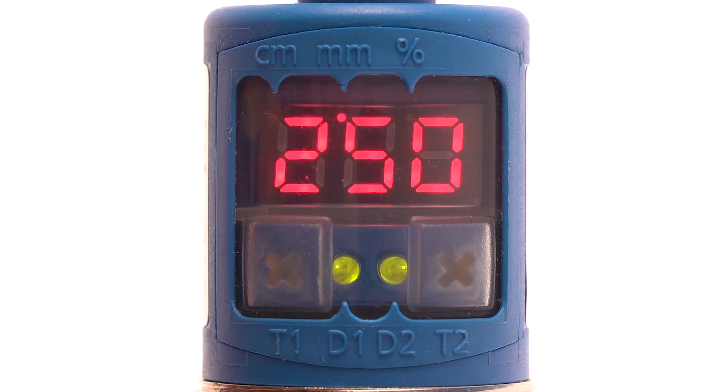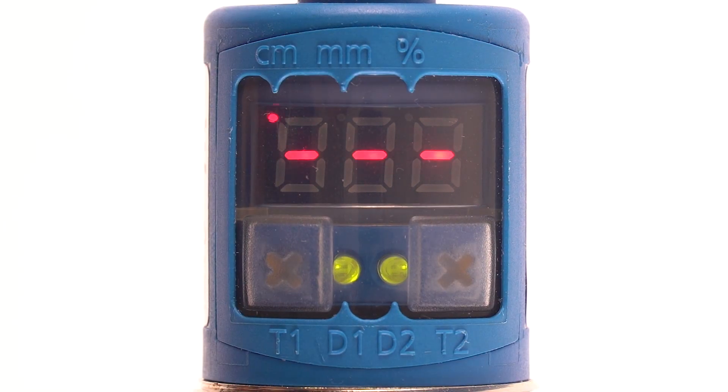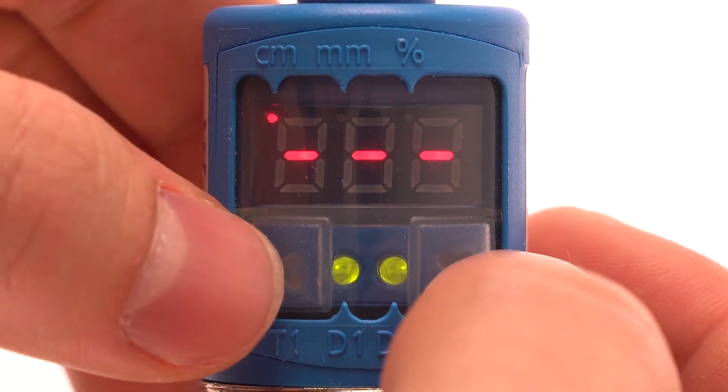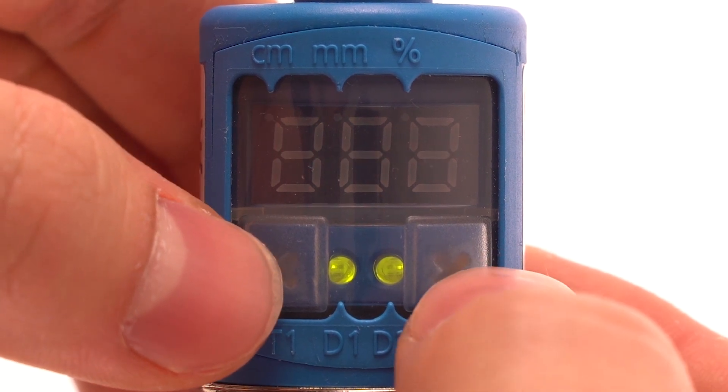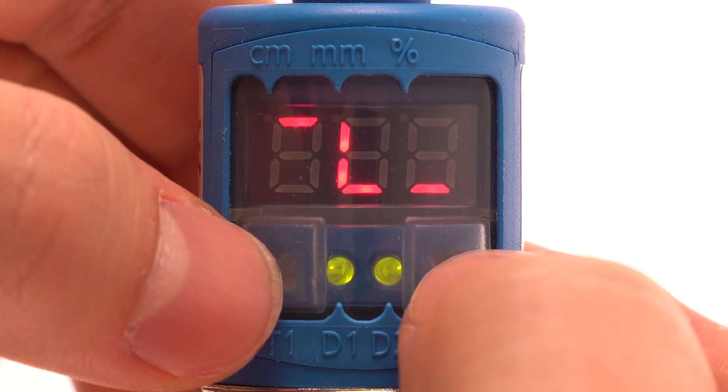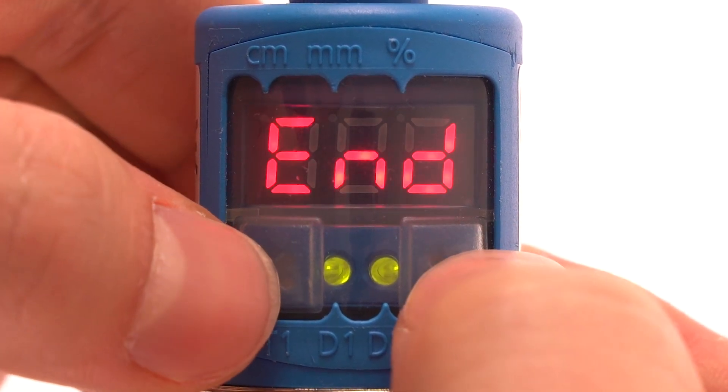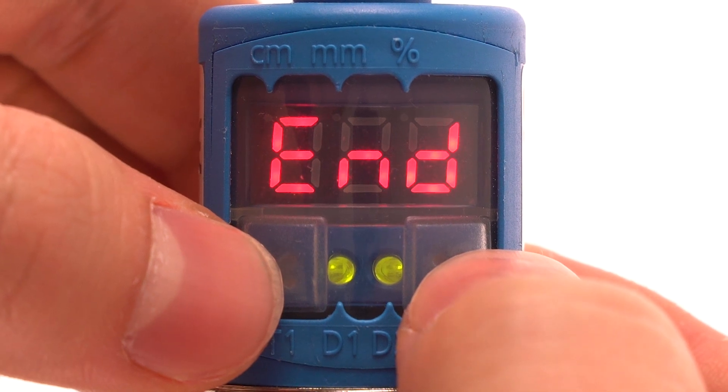Now simultaneously press T1 and T2. Three dashes appears on the display. For a simple switching point, simultaneously press T1 and T2. Select the normally closed or normally open contact. Simultaneously press T1 and T2 until end appears.